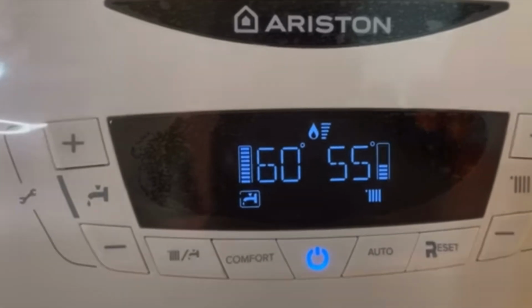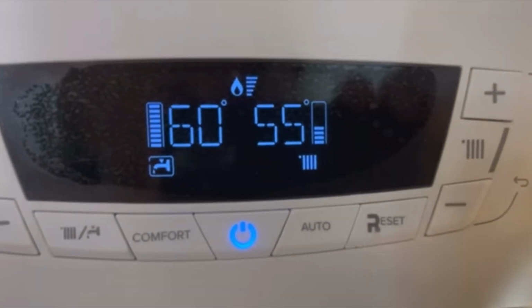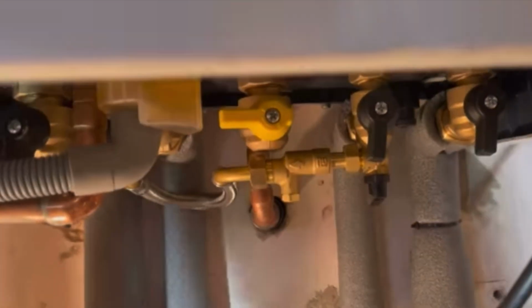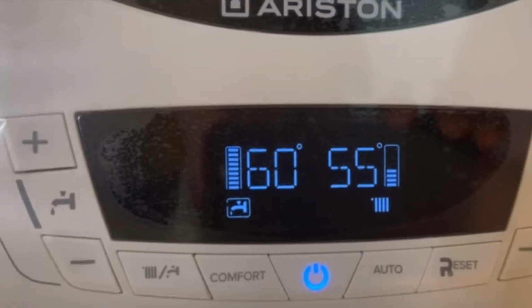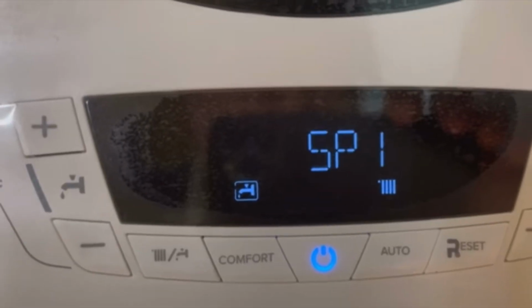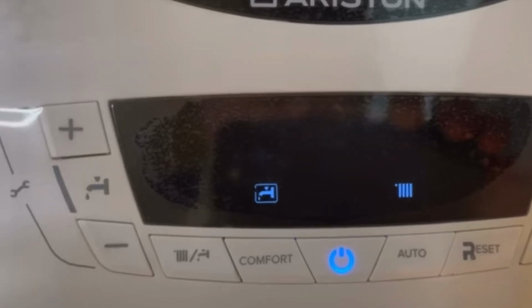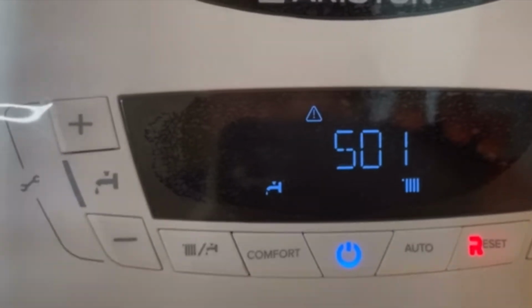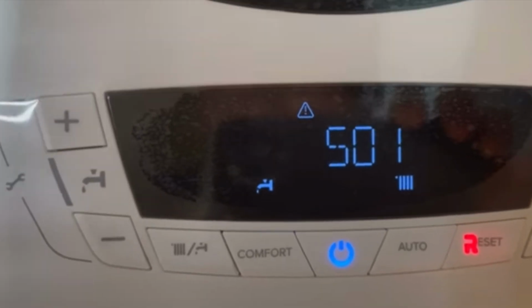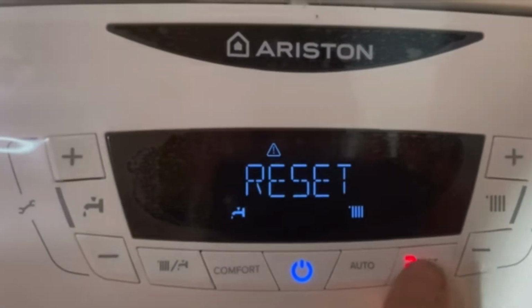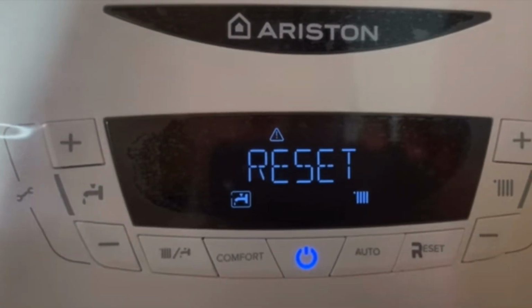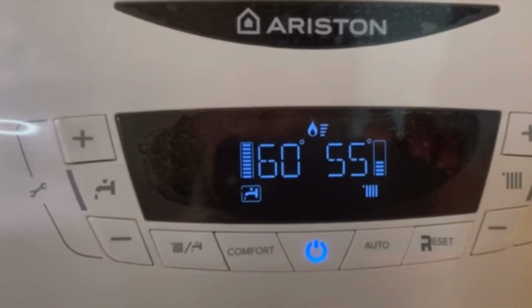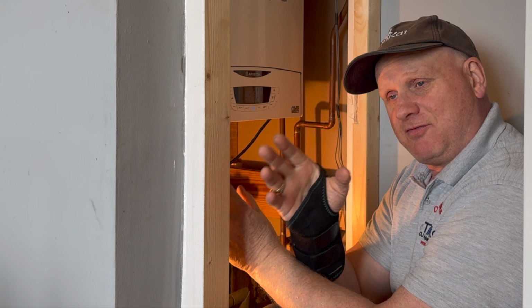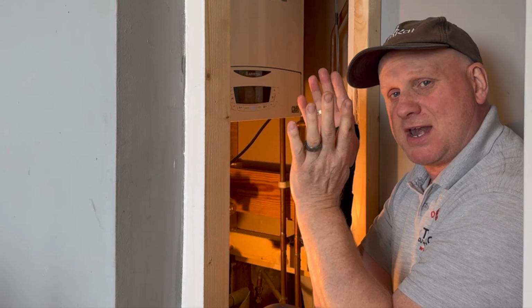So last test, safety devices. I've actually got the hot tap running. What I'm going to do is I'm going to turn off the gas supply under here. And then this should go SP1, SP2, SP3, and then it should lock out. And there you go, 501, it's got no gas. All I need to do now is turn back on the gas supply, press the reset button, and away it goes. So that's my look at the differences when you're servicing an LPG boiler to a natural gas boiler.